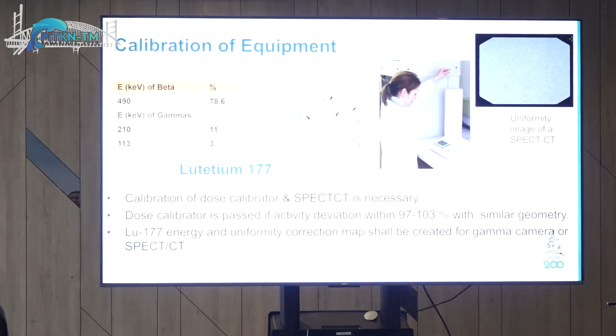So if you have gammas, not a problem, like lutetium, for that matter, even terbium as well has a gamma component in its decay, you can actually measure it. But not for yttrium-90, which is a pure beta. And basically, you need to worry about the geometry factors, right, in a dose calibrator setup.